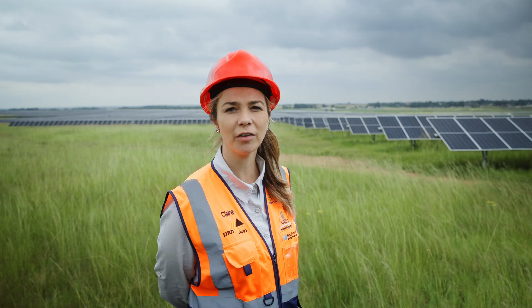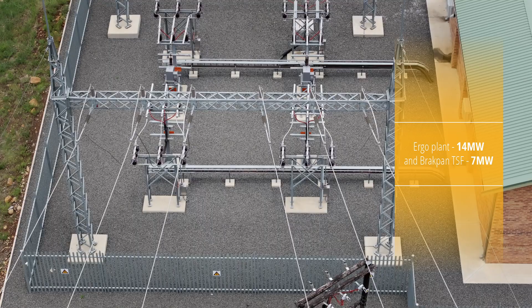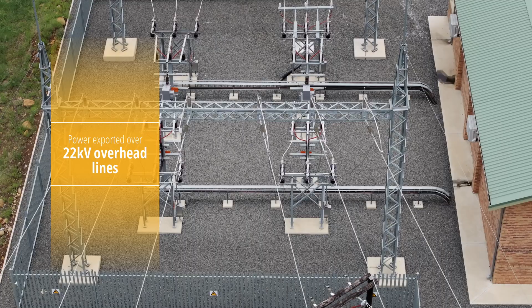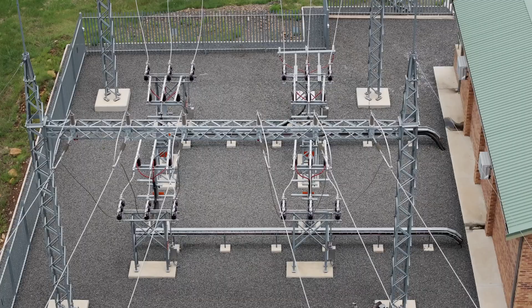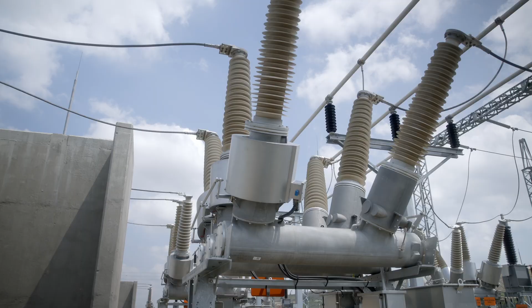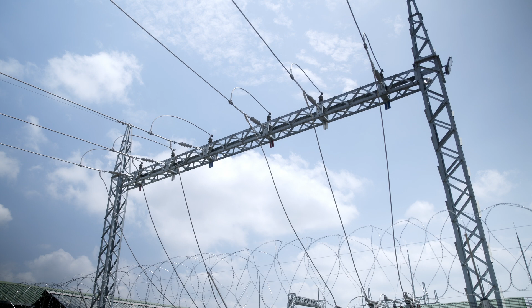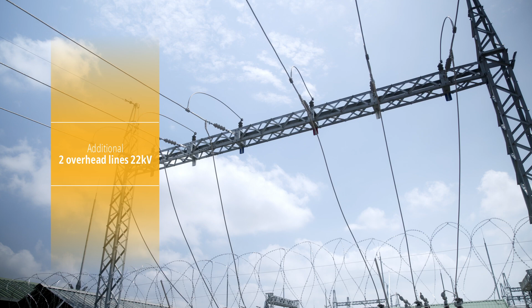The demand of the Ergo plant is around 14 megawatts and at Brakpan tailings 7 megawatts. The power is exported along 22 kV overhead lines, which were built at 33 kV. These overhead lines formed part of the project, as well as an upgrade in the Ergo plant. The Ergo plant was fed from an Eskom supply and is now currently being fed from the 2 new overhead lines. Furthermore, we've got an additional 2 overhead lines at 22 kV feeding Brakpan tailings.